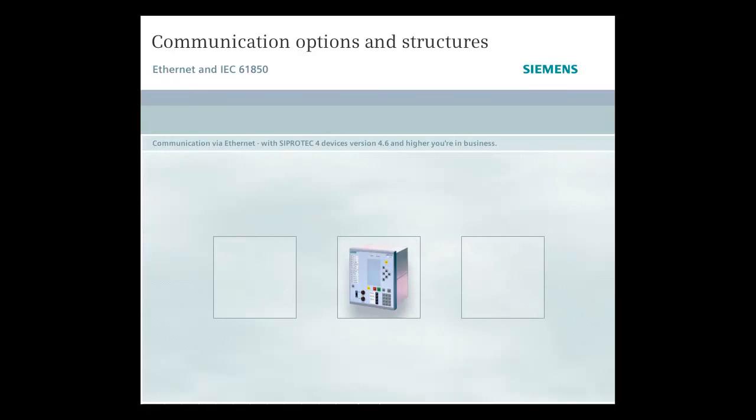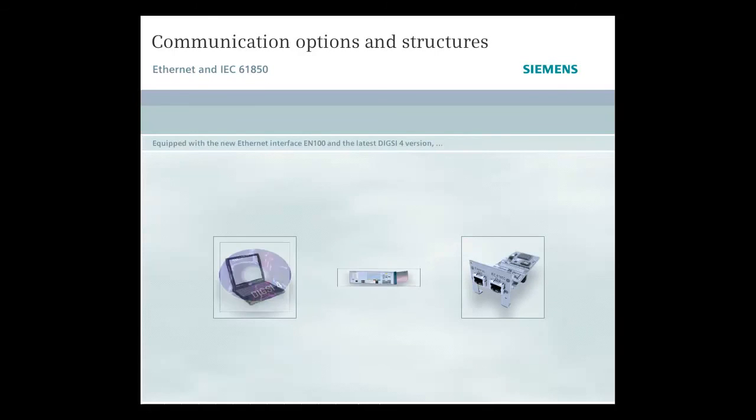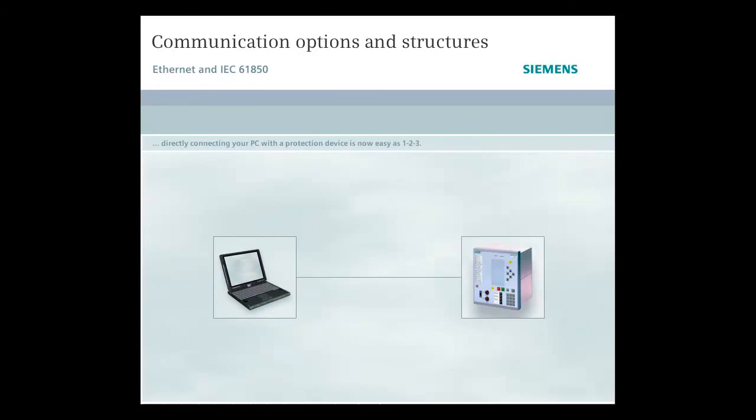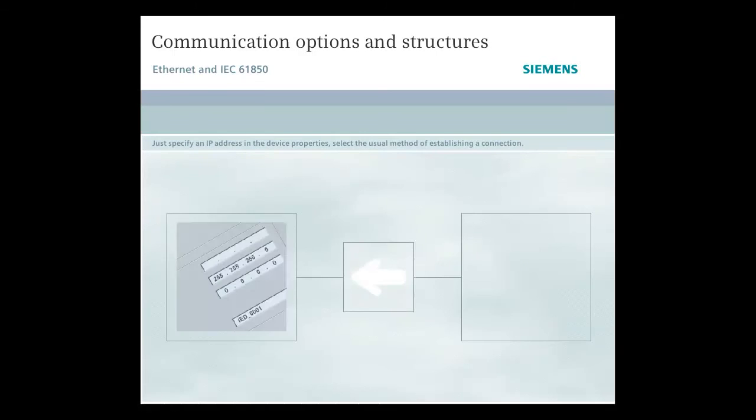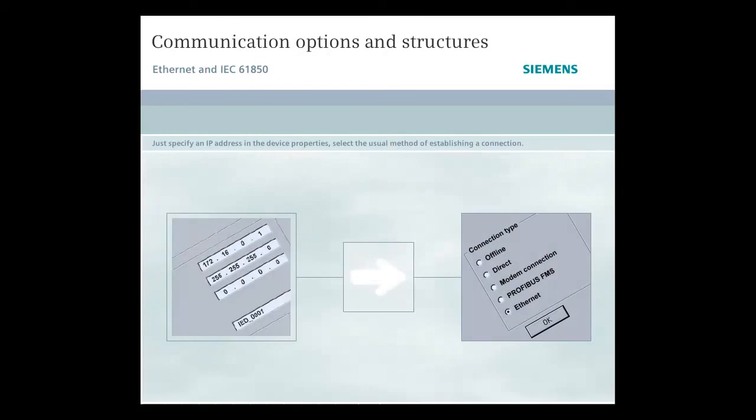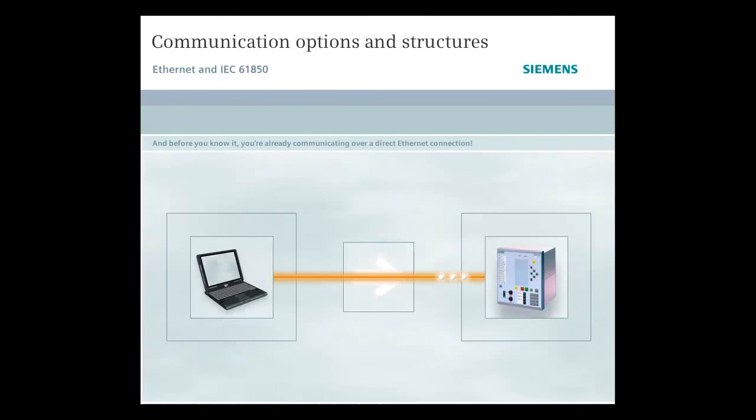Communication via Ethernet with SIPROTEC 4 devices, version 4.6 and higher, and you're in business. Equipped with the new Ethernet interface EN100 and the latest DIGSI 4 version, directly connecting your PC with a protection device is now as easy as 1, 2, 3. Just specify an IP address in the device properties, select the usual method of establishing a connection, and before you know it, you're already communicating over a direct Ethernet connection.